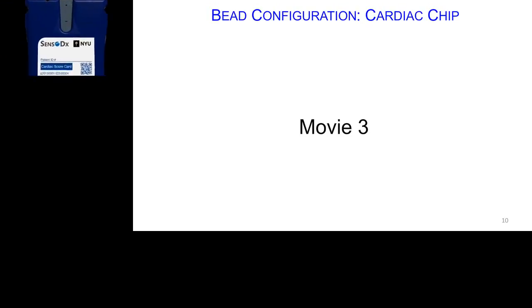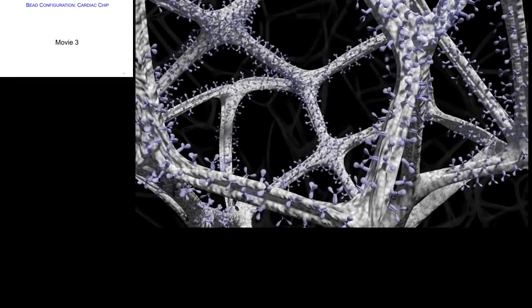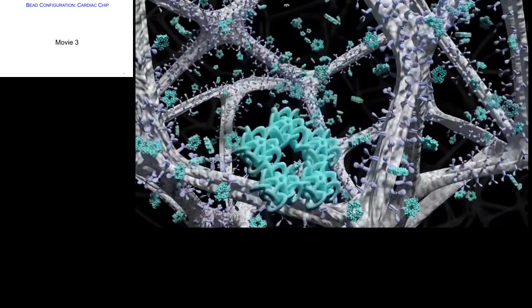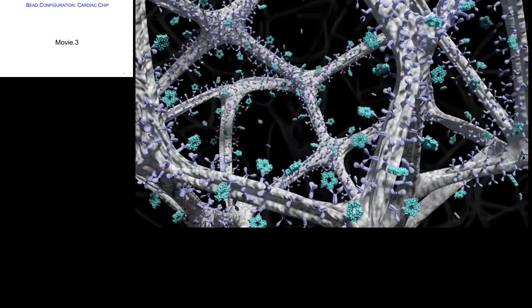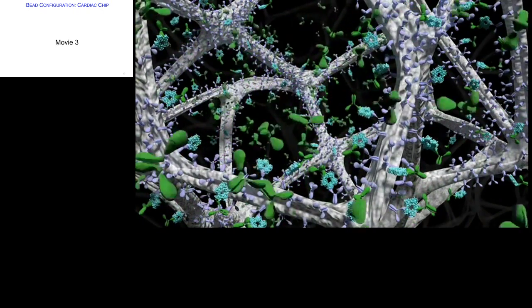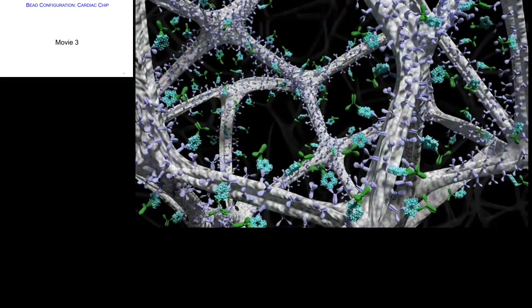Now let's look at the bead-based configuration of the lab card. The front end is basically the same. The bead serves as a microsponge with a nano-net, coated with a high concentration of a capture antibody. The pentameric protein CRP is sequestered from solution at the initial stage. It's not until we bring in the detection antibody — coated with green fluorophores — that we're able to visualize the presence of this protein at the very end of the assay when the green LED flashes.